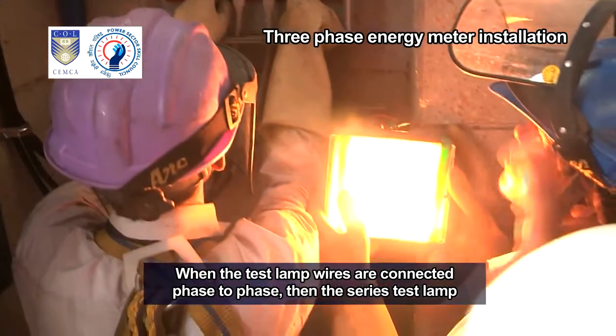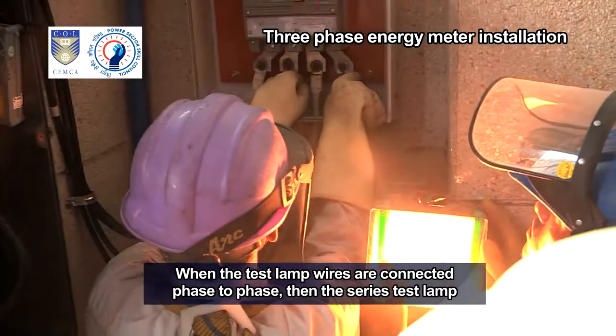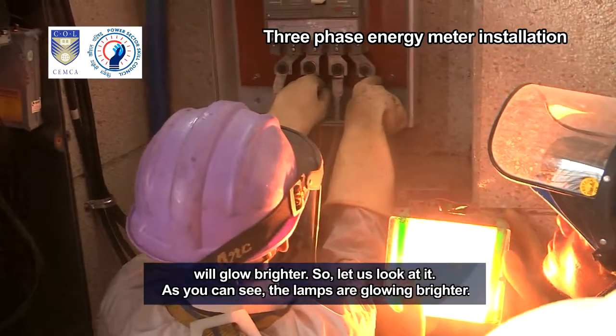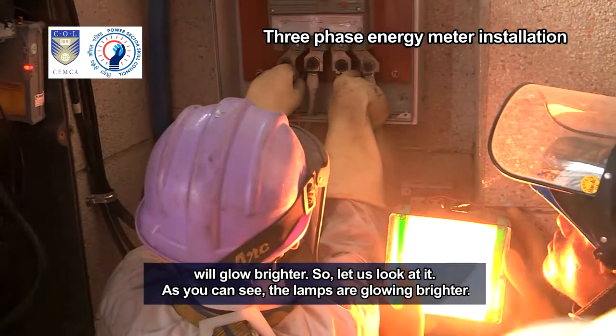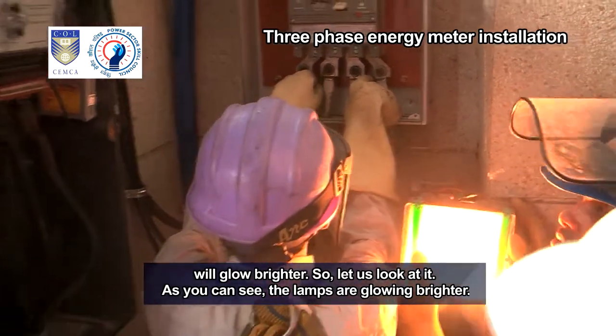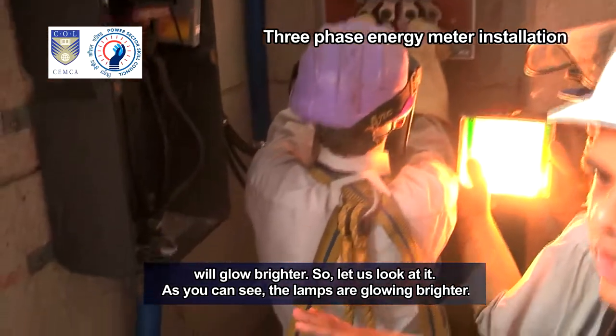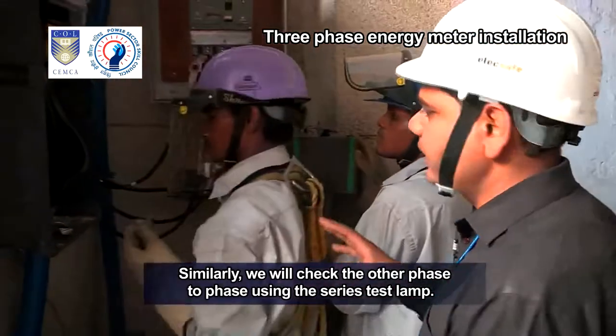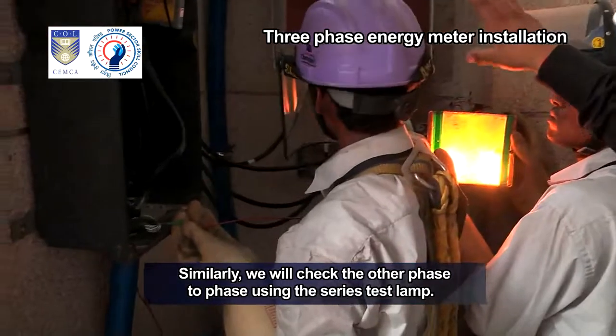When the test lamp wires are connected phase to phase, then the series test lamp will glow brighter. So, let us look at it. As you can see, the lamps are glowing brighter. Similarly, we will check the other phase to phase using the series test lamp.